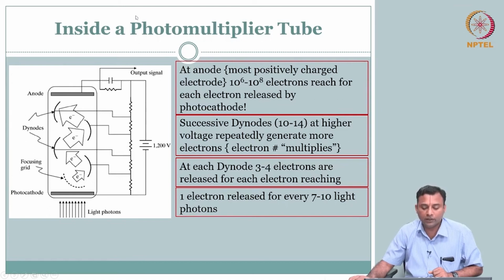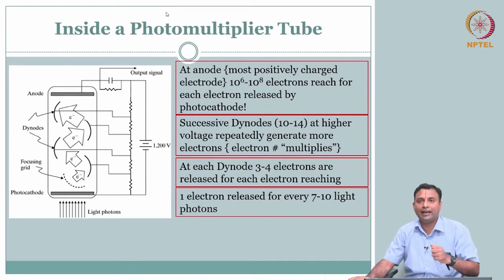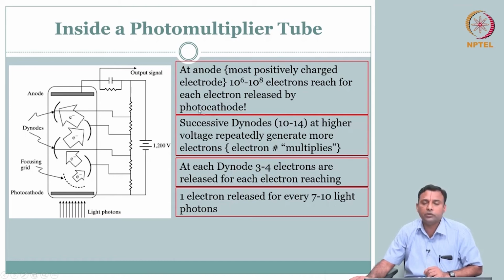Of course, you can read this out as a voltage signal, right. So you have successfully converted the gamma rays into light photons. The light photons converted to your electrical signal. So you can read this out, that is your output signal, okay. So you get some millivolts to volts, a few volts, in that range.